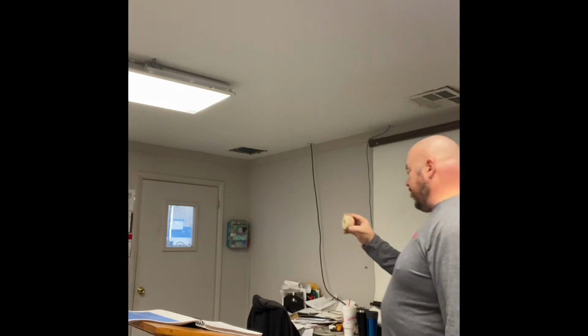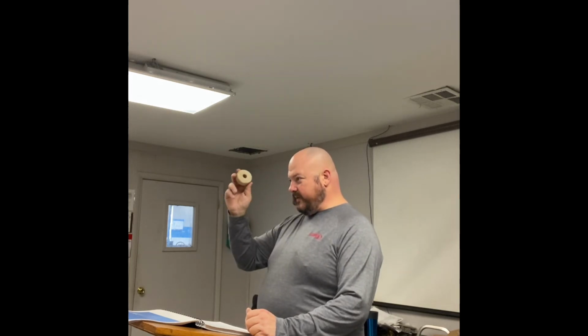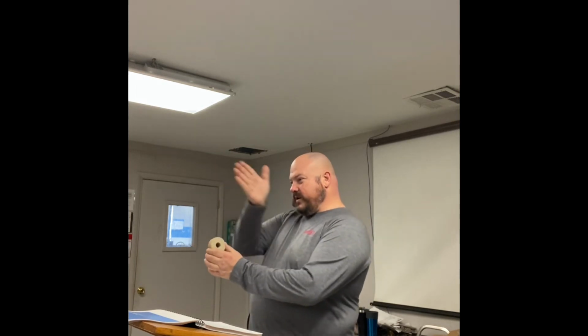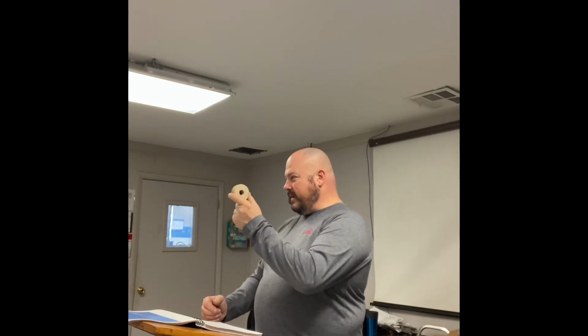Let's see here. We talked about high ambient, restricted, and restriction in your discharge line. Okay? So, when you have your line dryer, there it is. Your line dryer has a desiccant in it. This stuff right here is a filter dryer. And if you have a restriction, then it's going to create a problem. Okay, it's going to create a blockage, a backup. Easiest way to see if this is it is take a temperature reading on one side and take a temperature reading on the other side. If there is a lower temperature on this side, this has become a blockage problem.